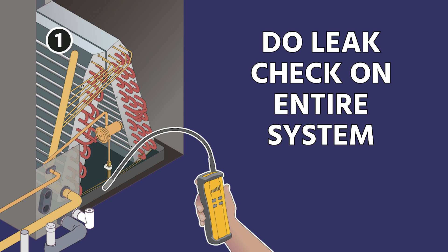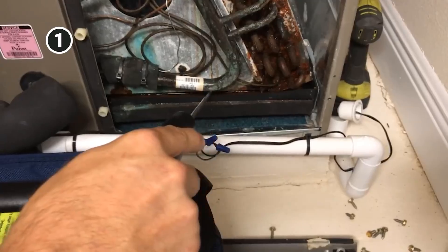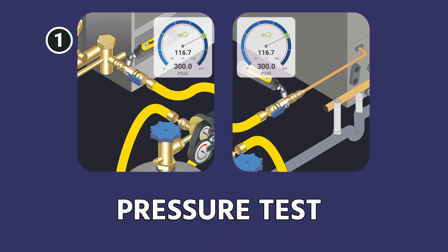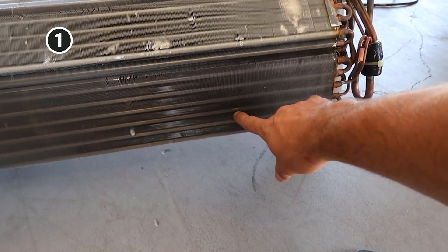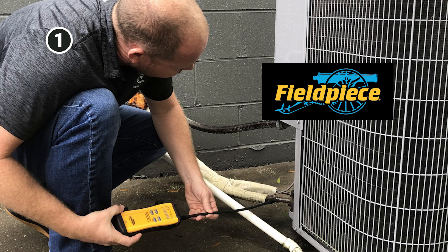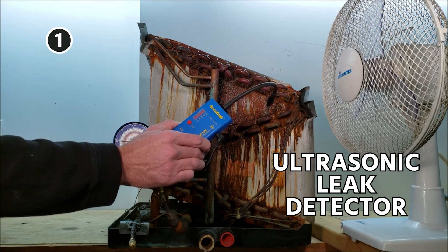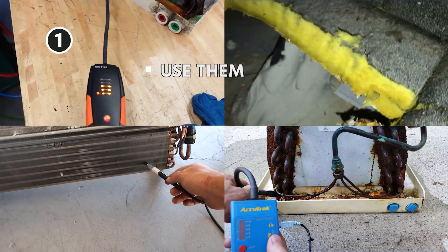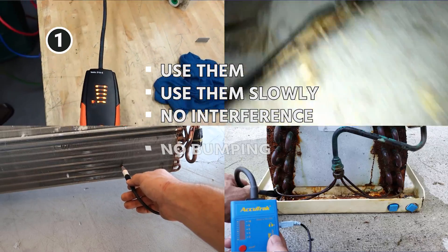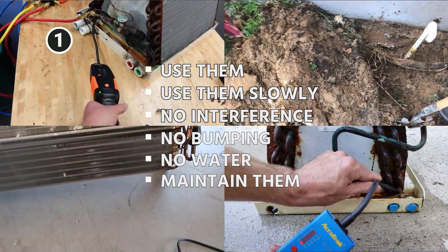Step one: do a leak check on the entire system to confirm no leaks are present everywhere you can get to. You need to do a proper leak detection — carefully and slowly go through the system. If you've got a small leak on a system with refrigerant in it, do an electronic leak detection. We suggest good quality leak detectors — we're showing a Field Piece leak detector here, the H10 from Bacharach is a really good one, and the Stratus from Inficon is one we use. We've also been experimenting with ultrasonic leak detectors.